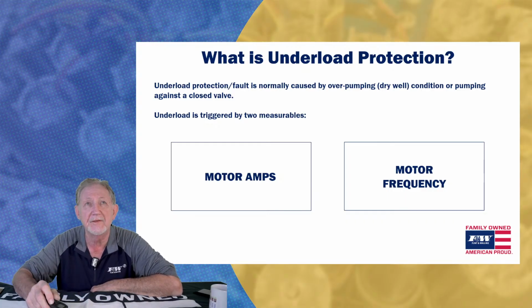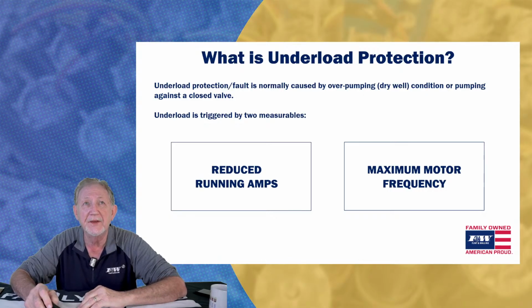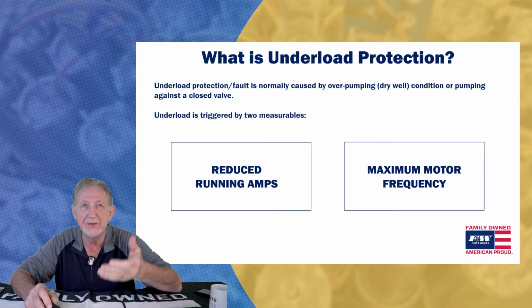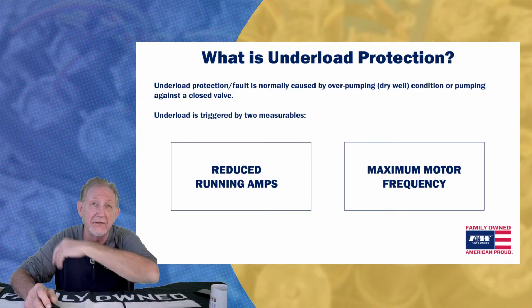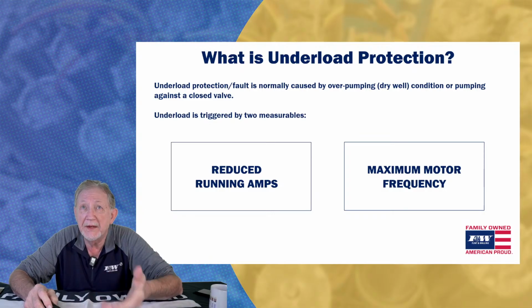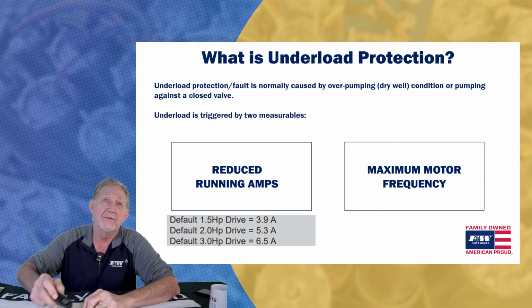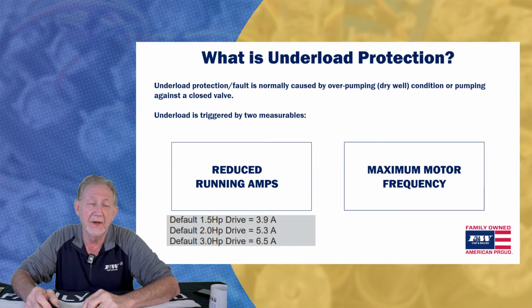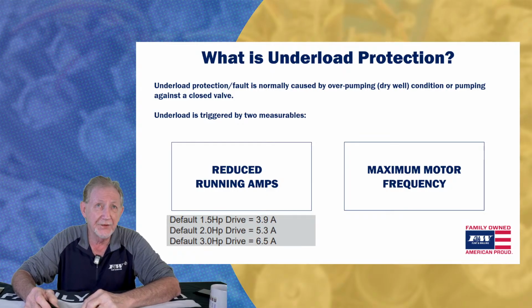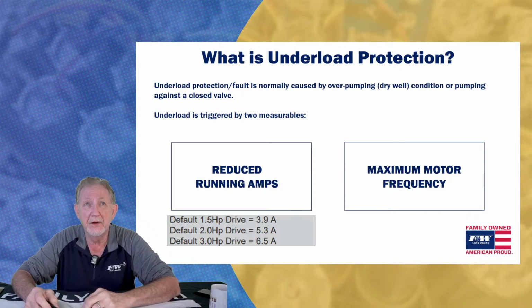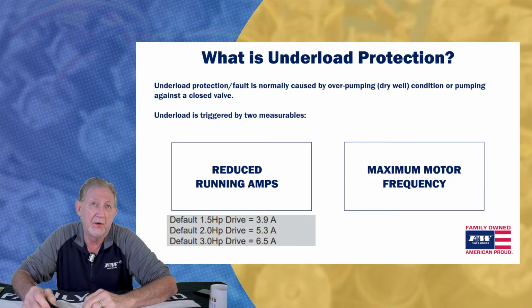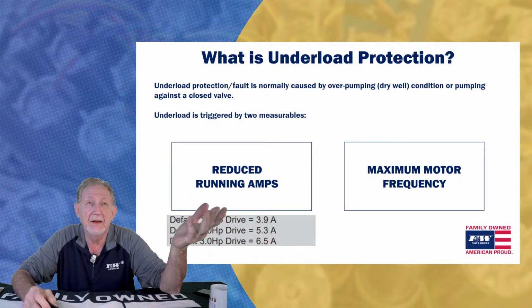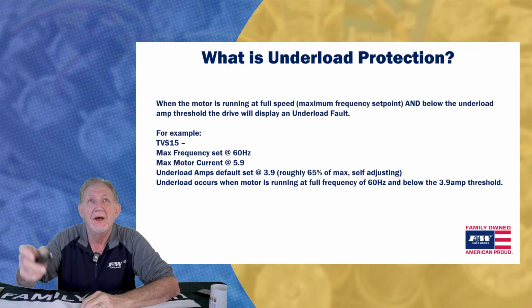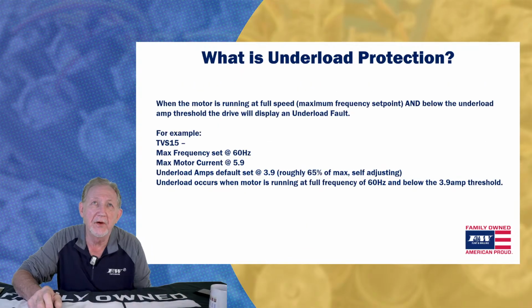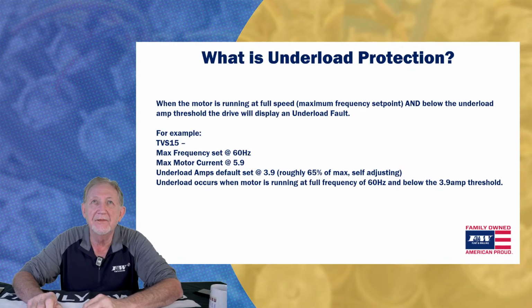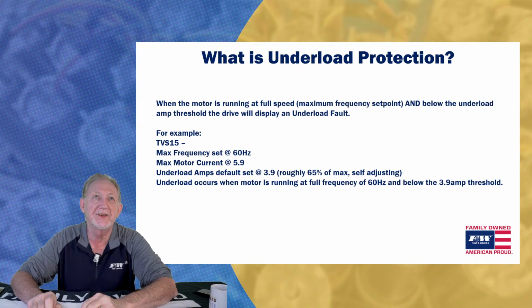Let's look at what happens. Well, first of all, if you're in an underload condition, you're going to have reduced running amps, all right? Your maximum frequency, you're still running at full bore, but the amps are coming down. Dependent upon the horsepower of the drive, when we set that max motor amps up front, it's also going to default to an underload amp protection here. So you can see, like on a horse and a half, that underload is going to be at 3.9 amps, right? So what happens here is that when the motor's running at full speed, so it's at maximum frequency, at that set point, running full speed, 60 hertz, all right?